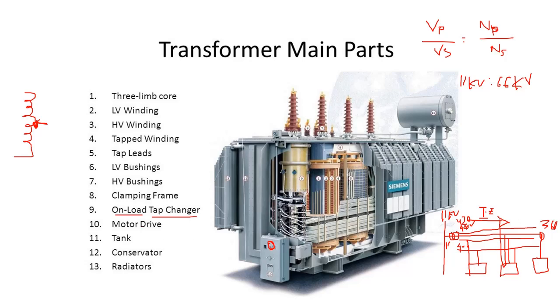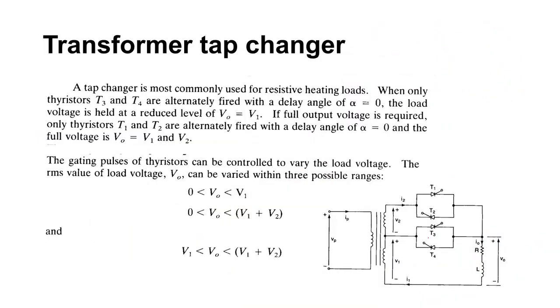In the on-load arrangement, you can do that when the transformer is connected. You can do it mechanically, or you can do it remotely. If you want to do it remotely without mechanical involvement, then you can do that by using a thyristor arrangement like this. With mechanical settings you cannot control the output voltage by changing alpha, whereas using a thyristor, first of all you can precisely control the output voltage, and secondly you don't have to physically go there. You can just give a trigger signal to the thyristor, and that will start the operation. So that is it for this lecture.